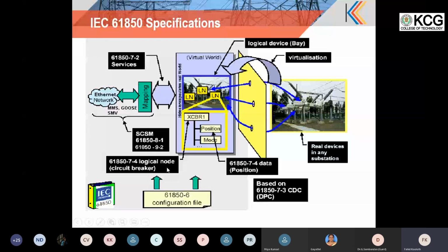Now once that is done, they have modeled all the system. Once they are modeled, they need to define an exchange mechanism to exchange this data. So they define an overview of exchanging this data, nothing but the abstract communication service interface, that is defined in the 7-2 standard. It details how I can operate a breaker, how to exchange the data from a system, my logical node, how to publish this logical node, how I can do a setting, how I can do a command, how I can publish my status, samples, everything. So the overview is defined in the abstract communication service interface, which is defined under 7-2.